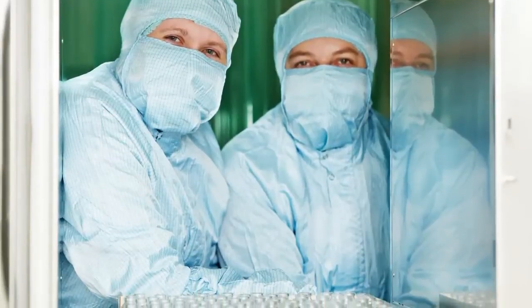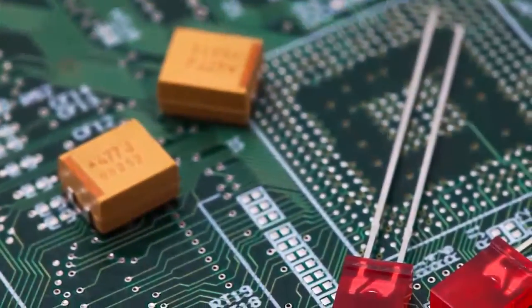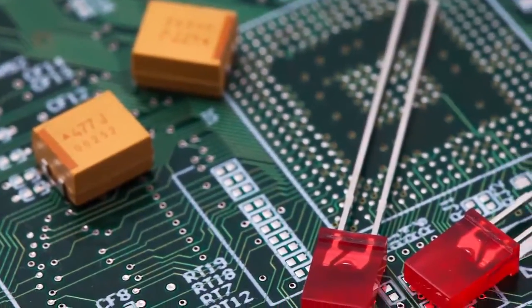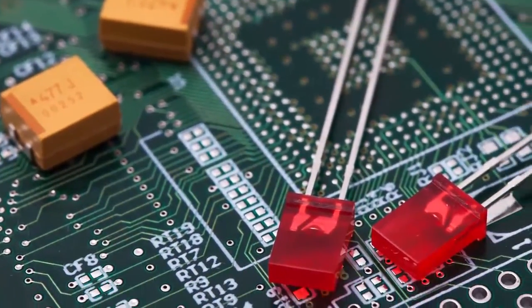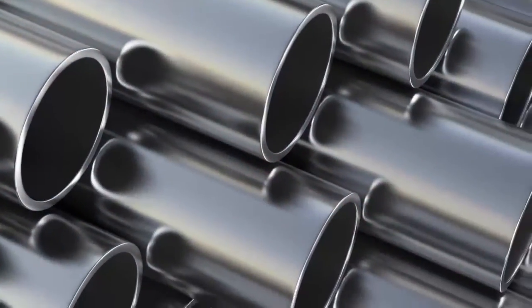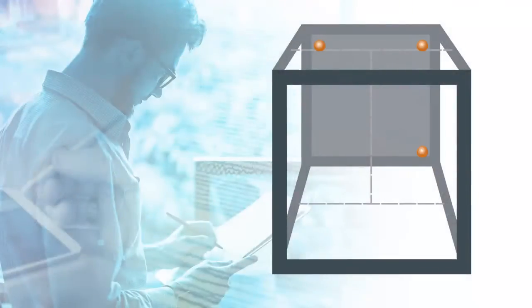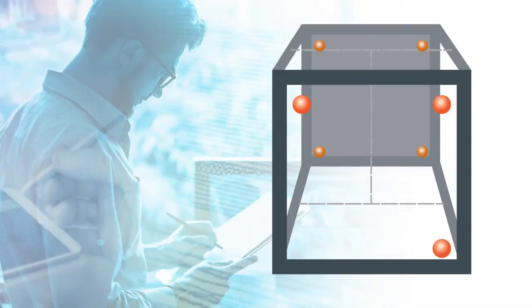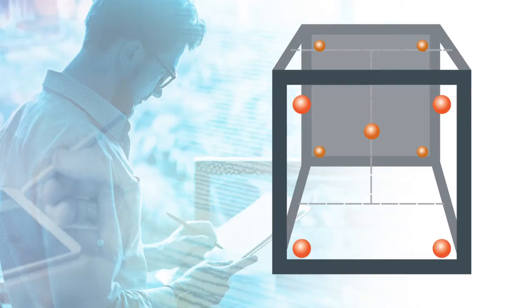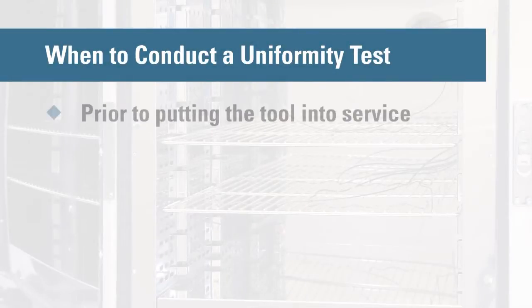Before implementing any critical thermal processing step, you need to confirm that the oven you are using is delivering the temperature uniformity required for your process. A nine-point uniformity test that measures temperature in every corner as well as the center of the oven will ensure that the temperature throughout the oven remains relatively constant. This test is normally conducted prior to putting the tool into service.